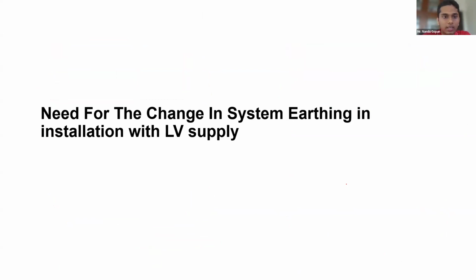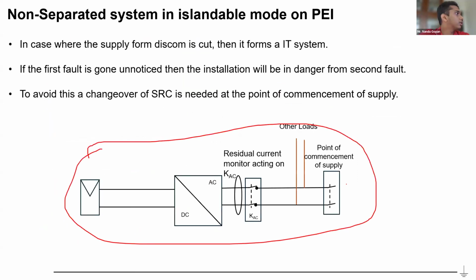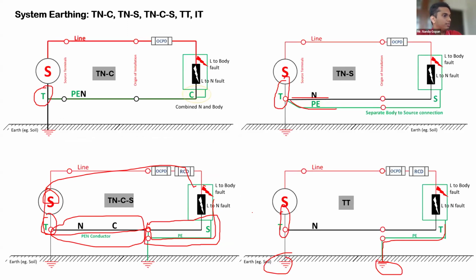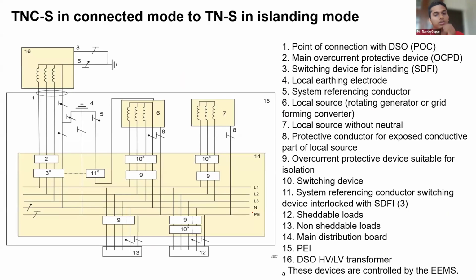Now, as I explained earlier, in the non-separated system, if the discom is disconnected here, there can be an IT system. So for this case, what are you supposed to do? I'm talking about an LV supply. This is the image from the prosumer electrical installation standard IEC 60364-8-82. I will show a much more simplified image than this. But first, I'll explain what this image is. Then I'll explain how the changeover happens from the TN-C-S to TN-S in islanding mode.